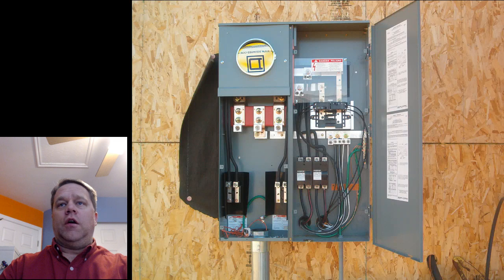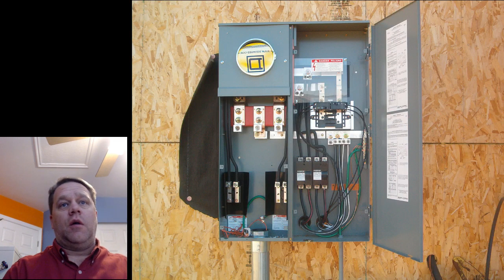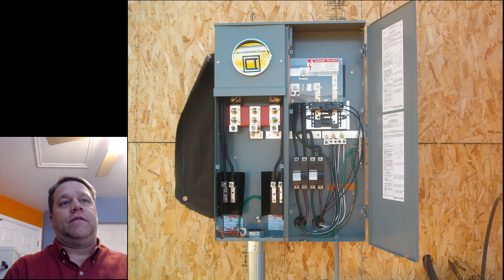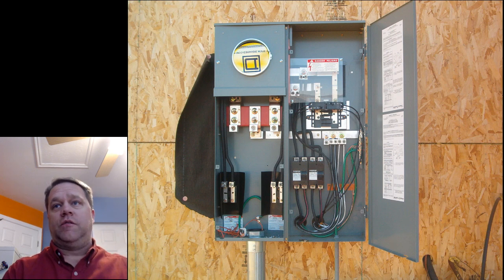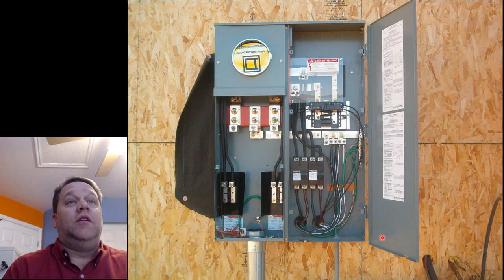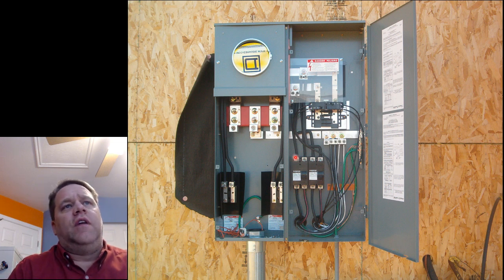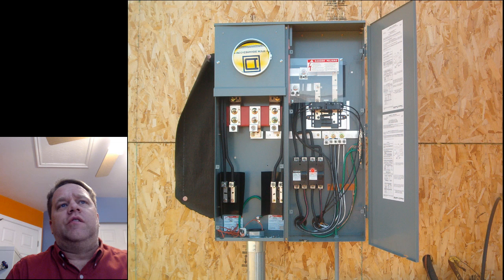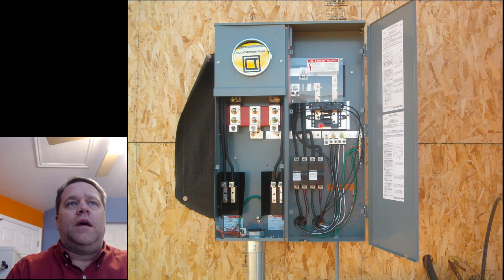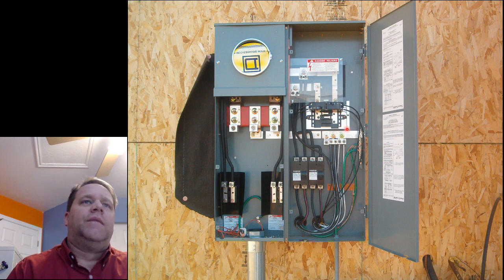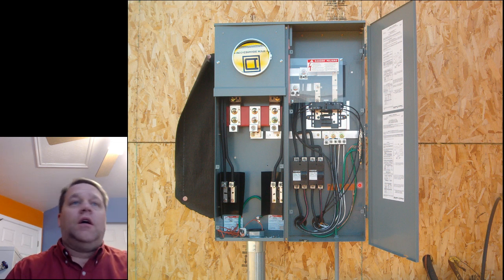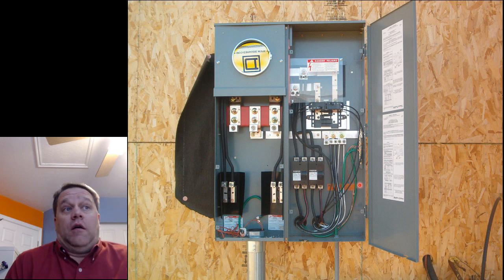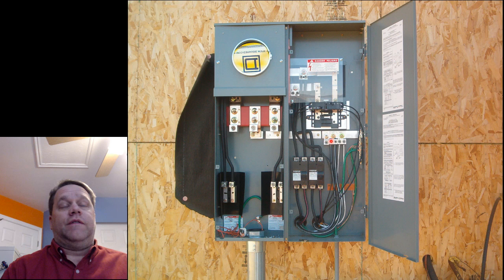So in my area, this is a really common panel board for service disconnect for a house, and this would not be allowed anymore. This panel is just prohibited, can't use it. So this is a 400 amp service. You'd have like two 200 amp breakers down here feeding sub panels, and then maybe, you know, an air conditioner and a detached garage, something like that. Very common panel board. I don't want to speak for any manufacturers, but this is not going to even be manufactured anymore.